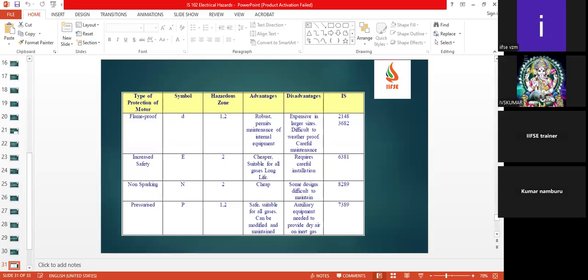Then pressurized, which is P, which can be used in zone 1 and 2, where the atmosphere can be created any time and also abnormal operations. Here also we have safe and suitable for all gases, can be modified and also maintained. Then auxiliary equipment needs to provide dry air and inert gas. Whatever auxiliaries are connected to this equipment should be provided with inert gas so that it helps the equipment in case of any short circuit or overload. Still, it will not allow the spark to come out of the electrical installations.